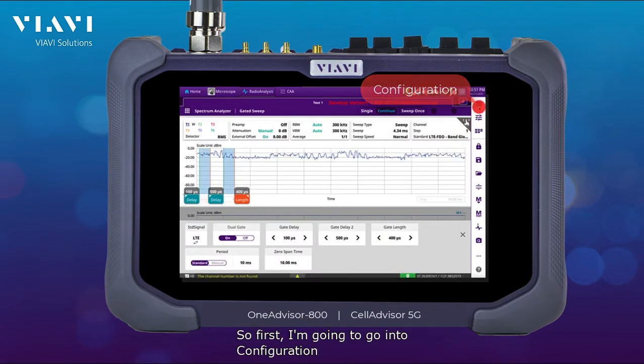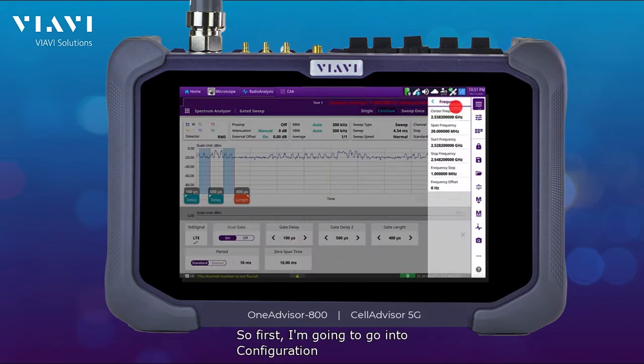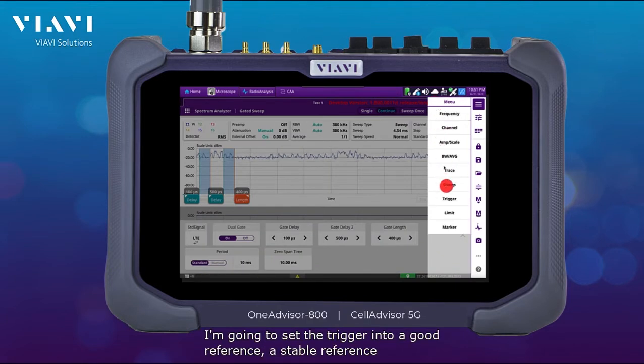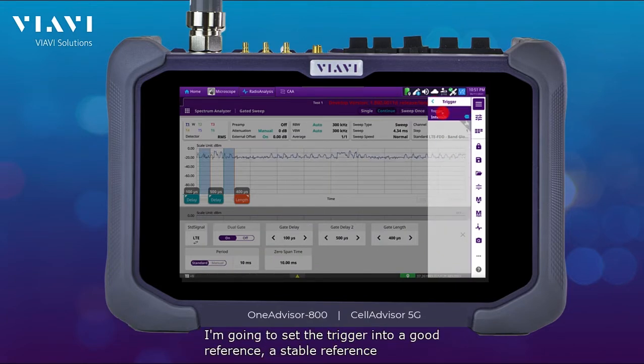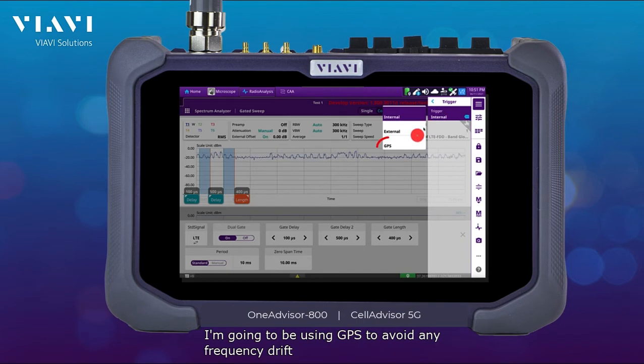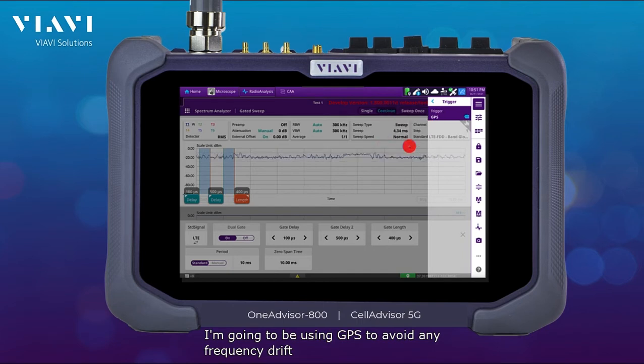First, I'm going to go into configuration and set the trigger to a stable reference. I'm going to be using GPS to avoid any frequency drift.